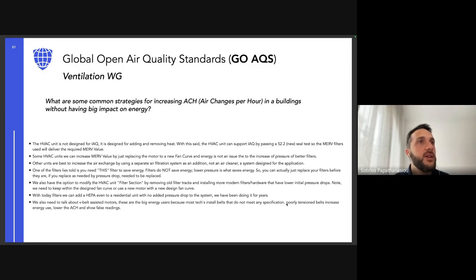Someone else said that on the filter side, you need these filters to save energy. Filters do not save energy. Low pressure is what saves energy. So you can replace your filters as needed, according to pressure drop.